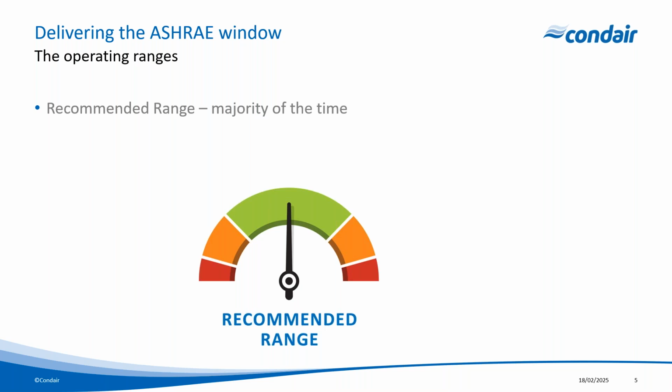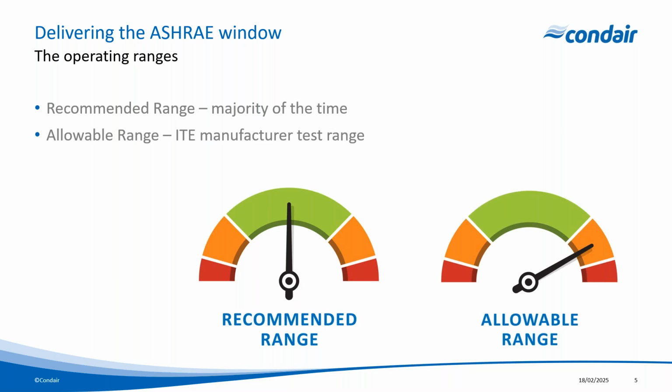Now, the allowable range is where the ITE manufacturers test their equipment to verify full operation. However, it's important to note here that this doesn't mean that there's not going to be any impact on the IT equipment. So although the equipment may function at the extremes of the allowable range, it may have an impact on the performance and the reliability of the IT equipment itself.